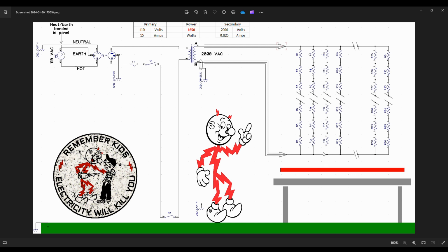If you put your hand on this block of wood, though, it could very well travel through you to ground. So you've got your insulating gloves and insulating shoes, dry and in good condition, tested and inspected. If you reach over and touch this block of wood, or touch this probe to reposition it while things are energized, as long as these protective items are theoretically in good condition, you're not going to get a current path through you to ground and back to where the current wants to get to.